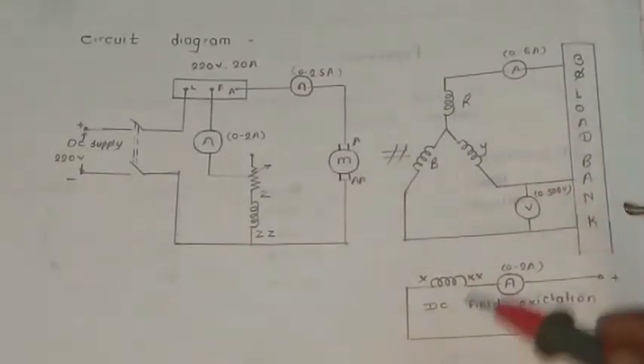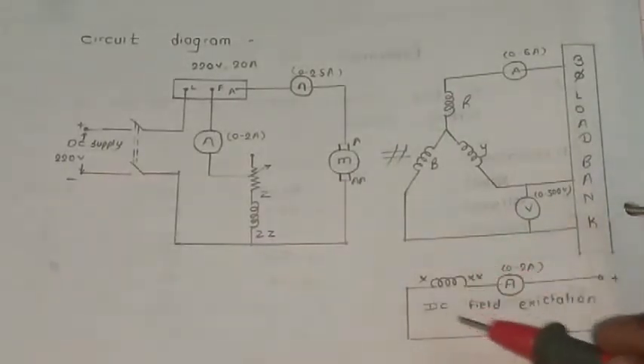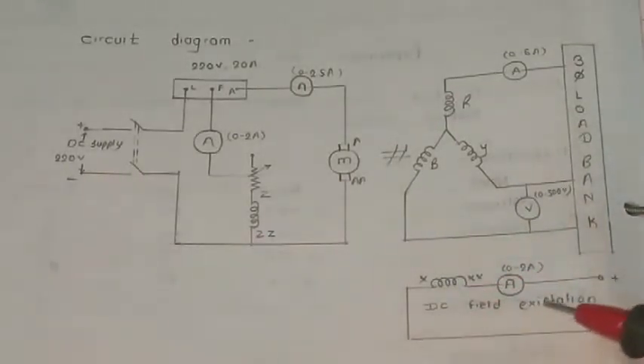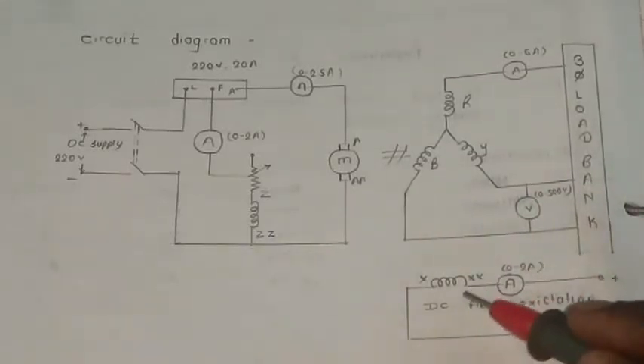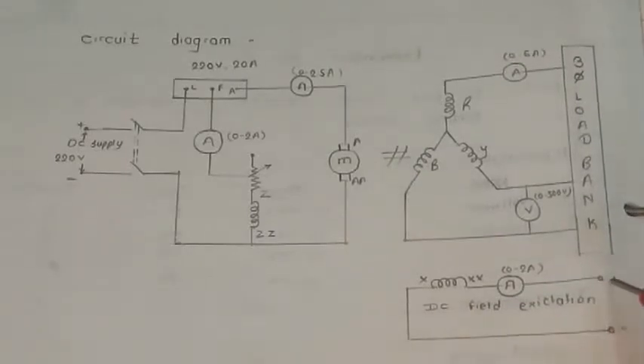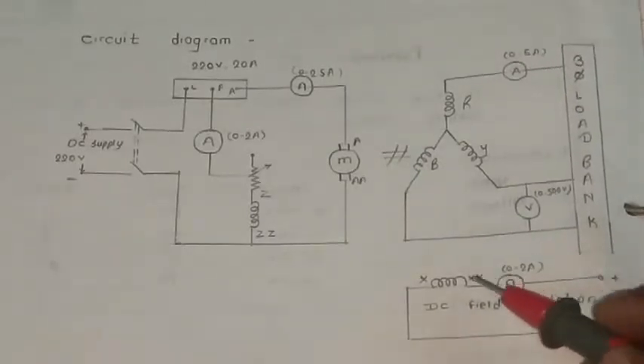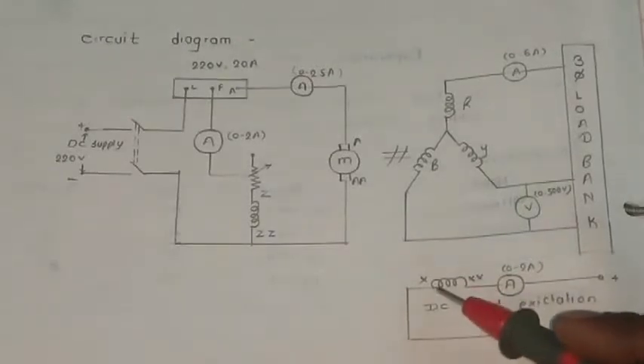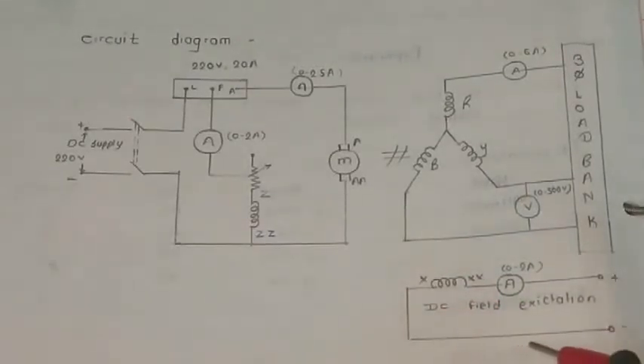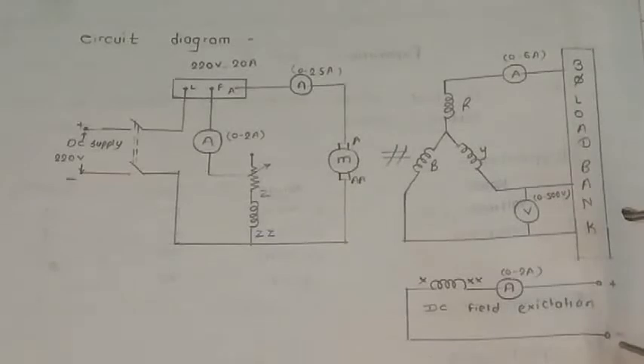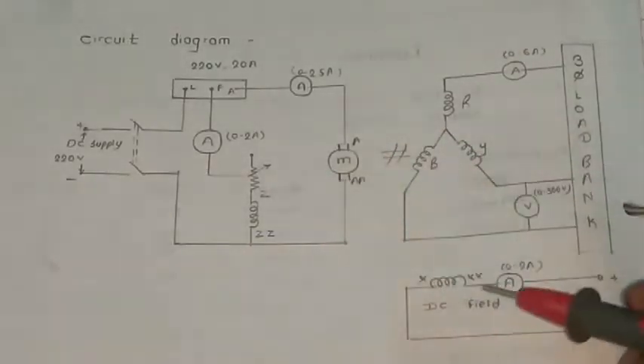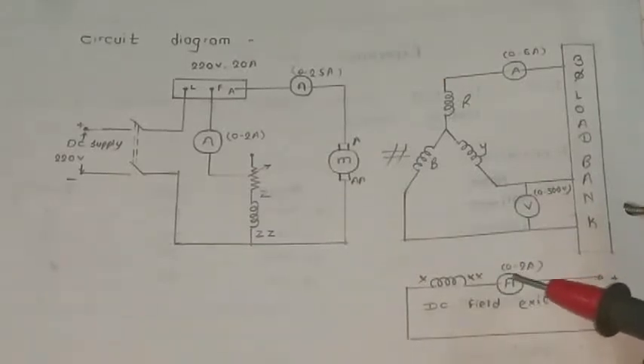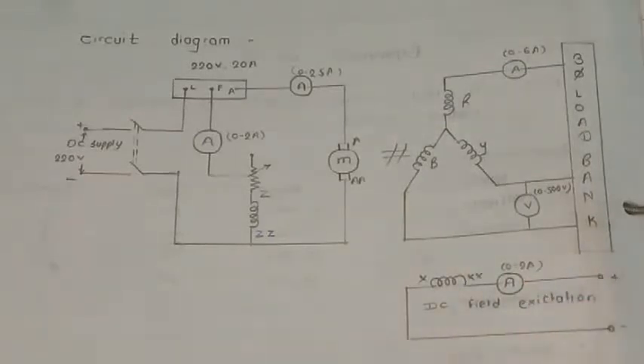This alternator is separately excited, so there is an excitation unit. We have to give a separate DC supply to the excitation unit, the DC field excitation. So the DC supply will go to the ammeter, the ammeter goes to the field winding of the alternator, and from the field winding of the alternator the supply goes back to the negative terminal of the DC supply. This is a simple circuit diagram of our practical to find the regulation of the alternator by direct loading method.